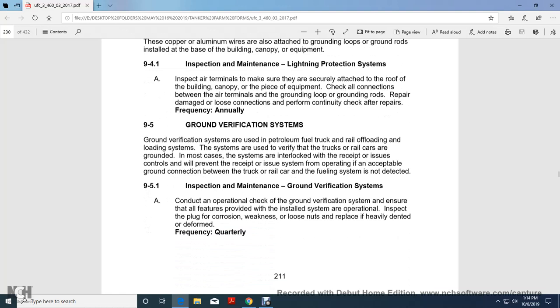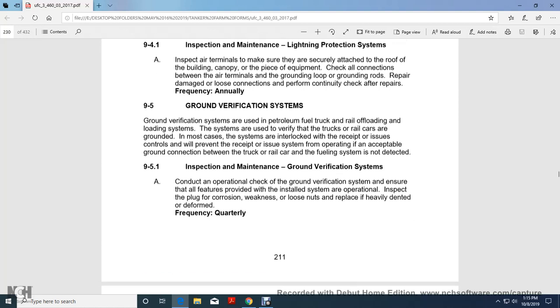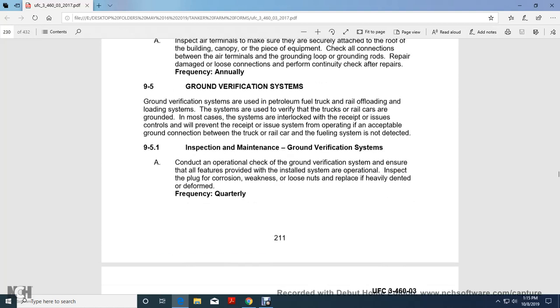Ground verification system. The ground verification system is used in fuel truck and rail offloading and loading systems. The systems are used to verify that the truck and the rail cars are grounded. In most cases, the systems are interlocked with the receipt and issue controls to prevent the receipt and issue system from operating when an acceptable ground connection between the truck or rail car and the fuel system is not detected.